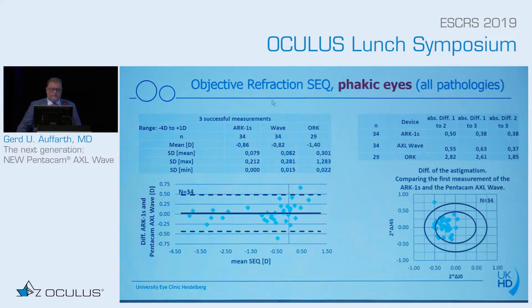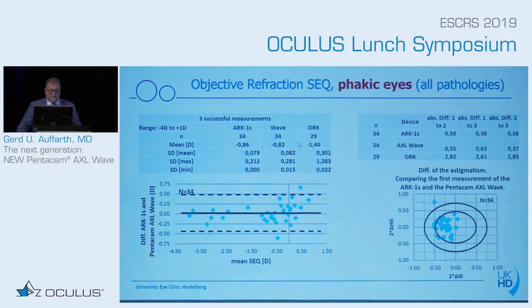When we look at the objective refraction — the spherical equivalent of the phakic eyes — including all patients, we have more or less identical values between the NIDEK and the Pentacam device, with a mean value of around 0.8 to 0.9 diopters. Interestingly, the Schwind device showed something quite different here. But we had very good agreement between the NIDEK and the Pentacam devices.